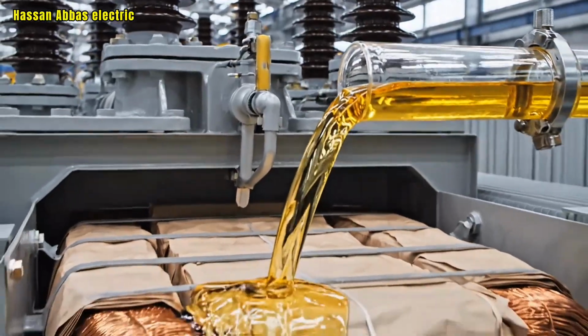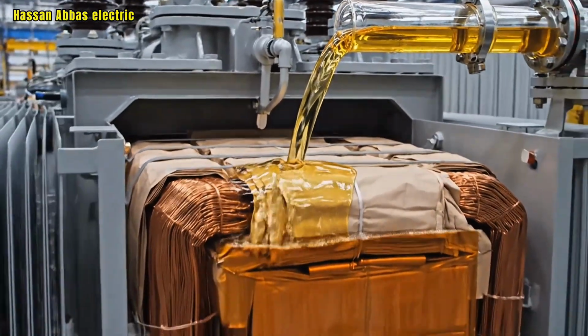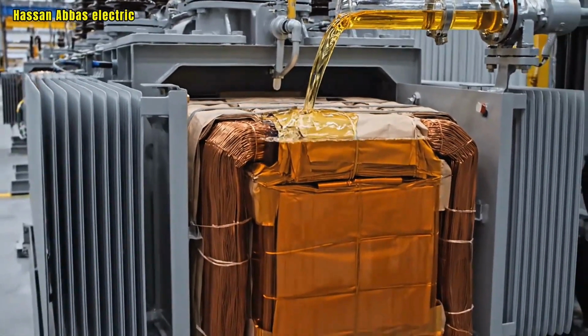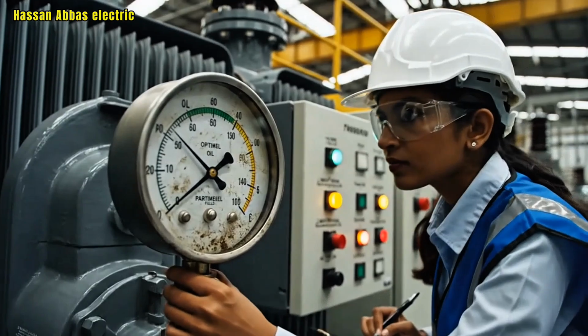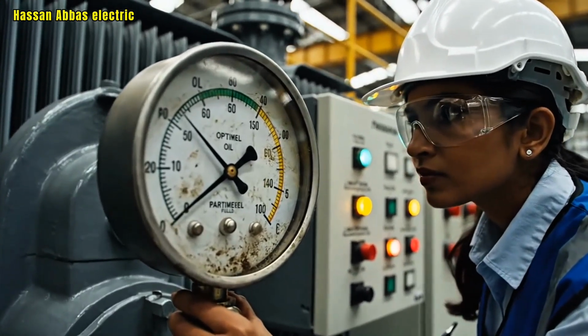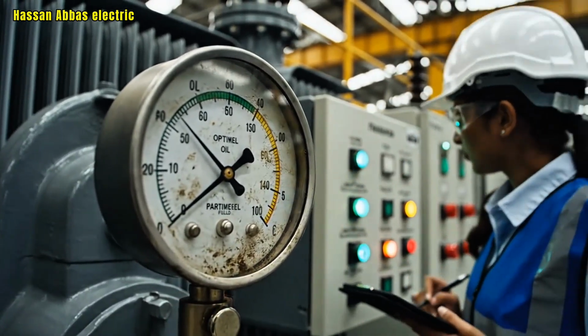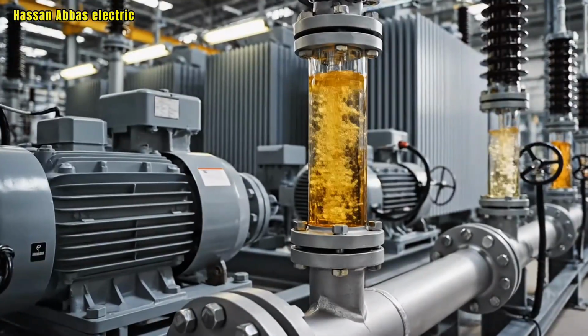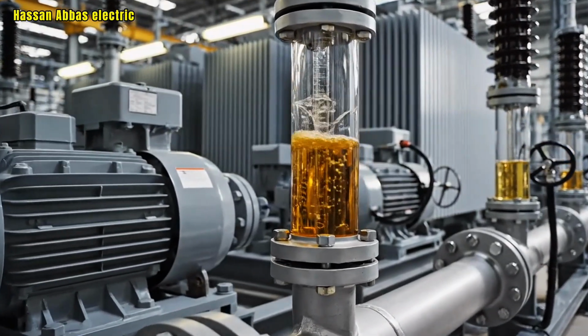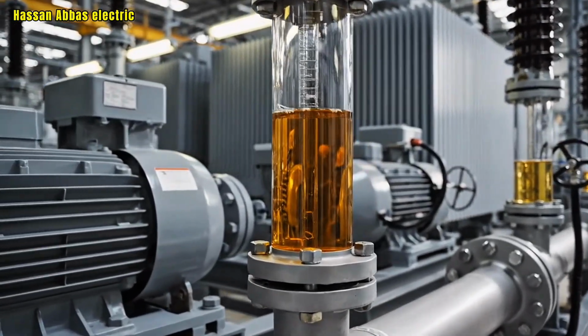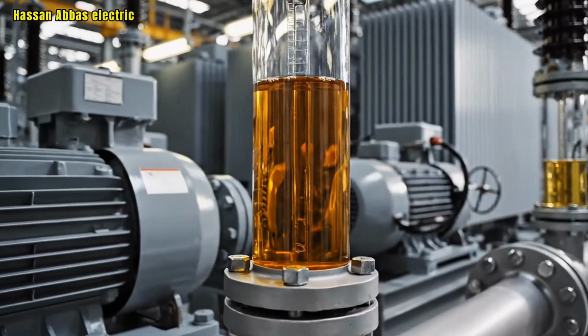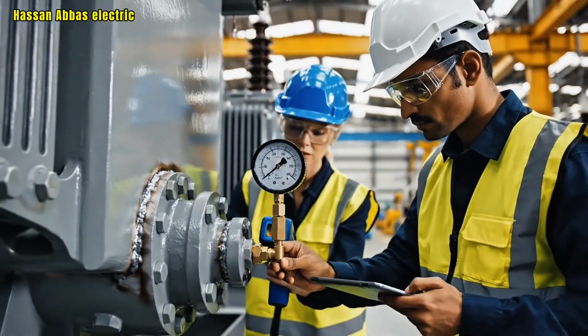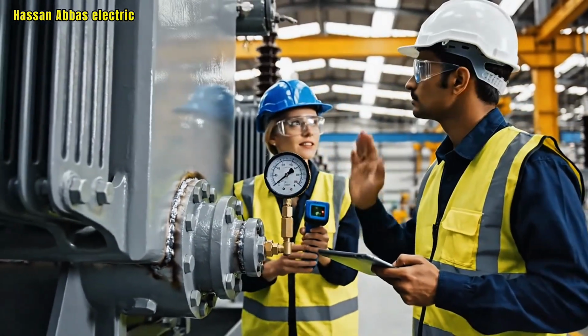Insulating oil is filled under vacuum to remove trapped air. Oil levels are carefully monitored during filling. The oil is circulated and allowed to settle properly. Leak tests confirm the tank is oil-tight.